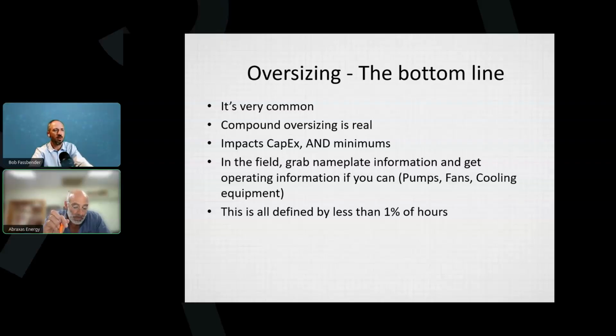Okay, so what if I had an air handler, I don't know, what they call built up air handlers. You go and it says on the label, I don't know, 100,000 CFM. We know what the fan motor size is. Is there an oversizing problem there? It's an existing building. I'm not modeling a new facility. I'm modeling an existing building. Is that an oversizing problem? Depends what you're doing with it. Okay, and so let's say maybe I'm going to convert it to a variable air volume system or something like that.